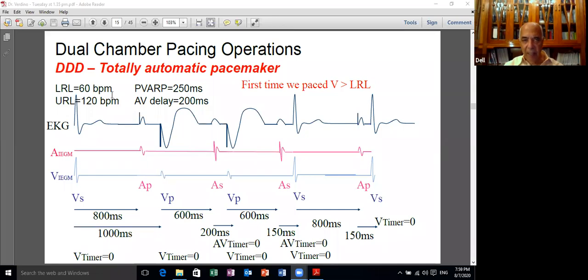In a VVI pacemaker, we can never pace more than the lower rate limit. But because we are tracking the atrium, if the atrial activity is faster, then tracking the atrium will result in pacing the ventricle at more than the lower rate limit. Now, having said that, we look into a more complicated situation.